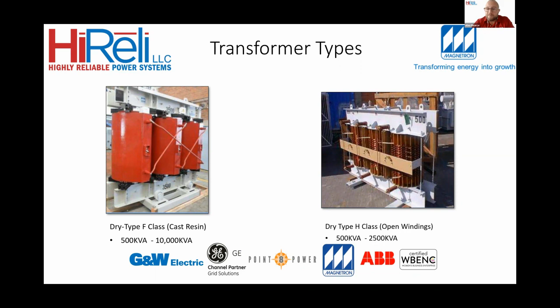Getting into the dry type transformers, they have an F class and an H class. Your F class is cast resin, and then your H class is where your windings are open air. Same range, or actually I take that back. The dry type with cast resin F class goes from 500 kVA to 10,000 kVA for their wheelhouse, whereas the dry type open windings is 500 kVA to 2,500 kVA.